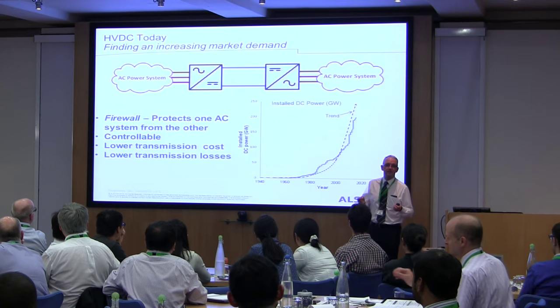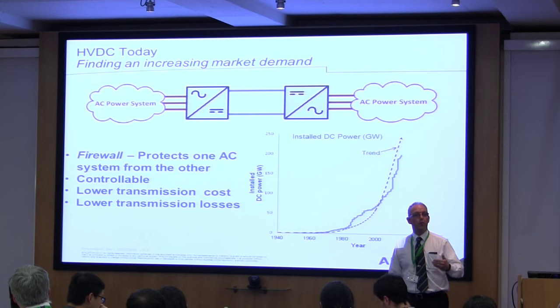Why do we do it? Besides keeping me employed, it provides a firewall between networks. Systems that are connected with DC allow us to control the power flow even during fault events. If you have a fault in one network interconnected with AC, the other network will automatically see the same fault. With DC interconnection, we can control the contribution to supporting your neighbor — we can automatically regulate power flow based on the frequency of the network we're connected to, helping only to the amount we can safely allow without risking our own power system.